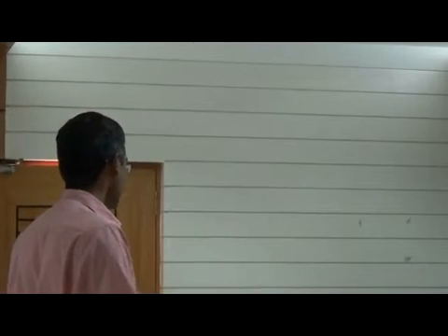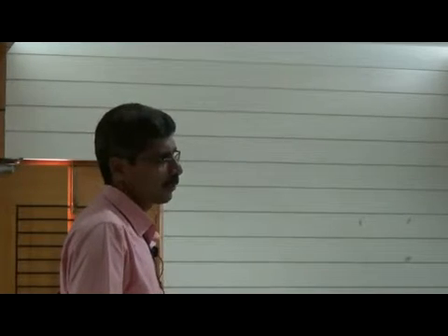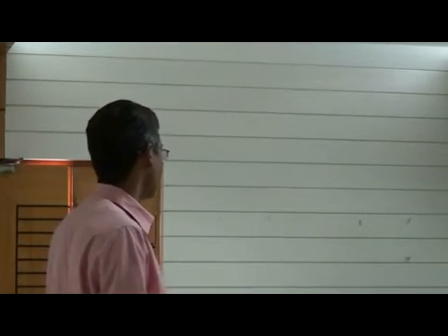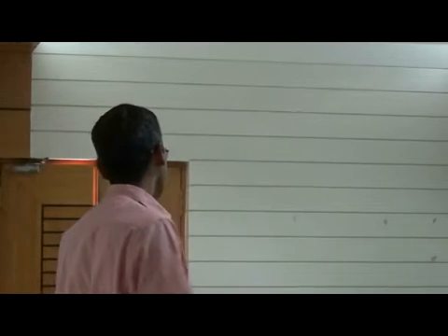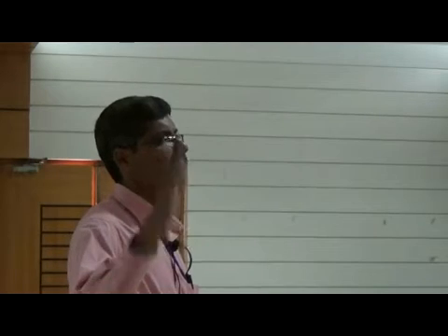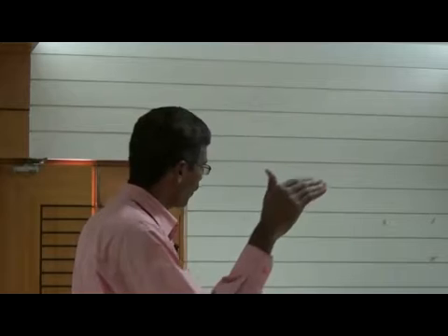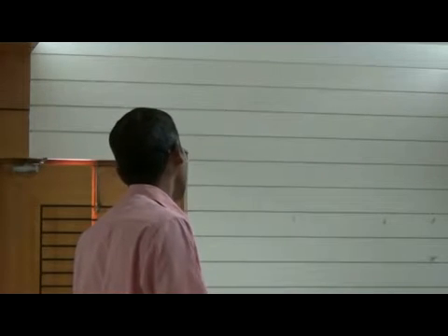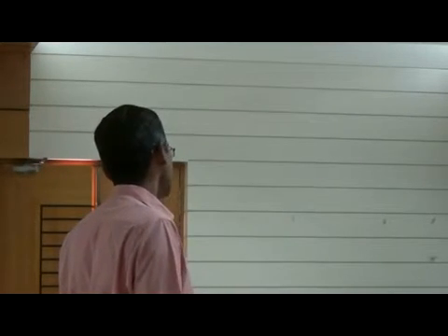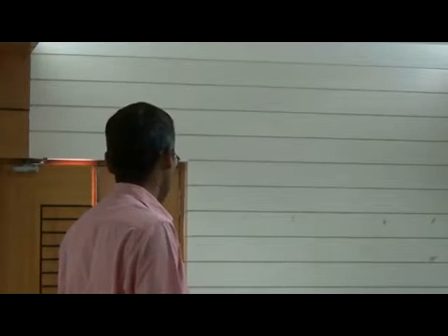I am assuming that the power factor is unity. Accordingly you can change it. So a 5 kVA generator I will buy for that, without the minimum load conditions. Then when it exceeds 5 kilowatt and is below 15 kilowatt, let us assume that the next size we will select is one 10 kVA alternator, diesel generator. So when the load demand is less than 15 kilowatt, you can use that 5 kVA generator as well as the 10 kVA generator.